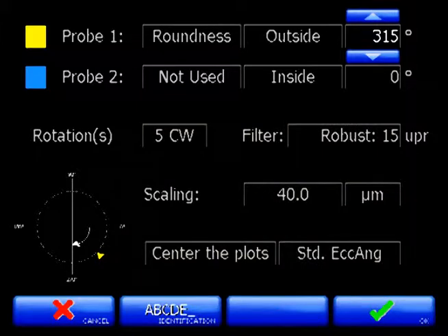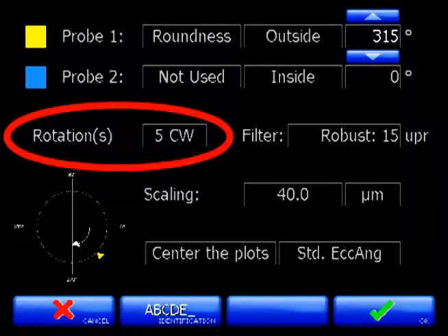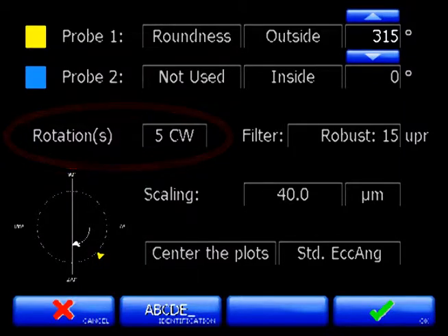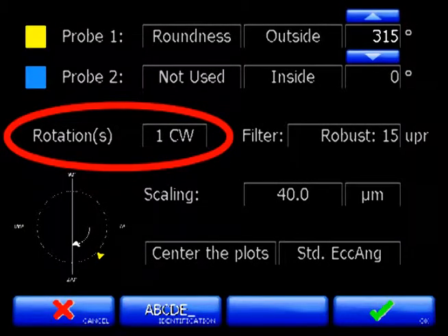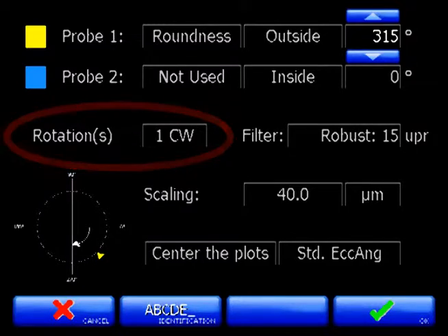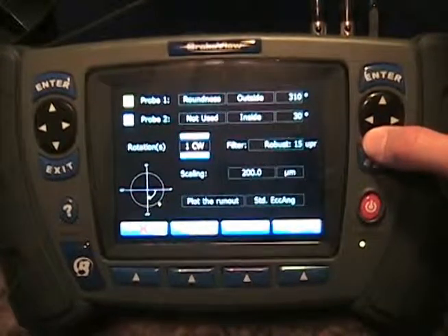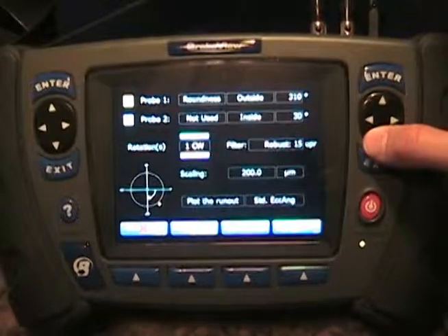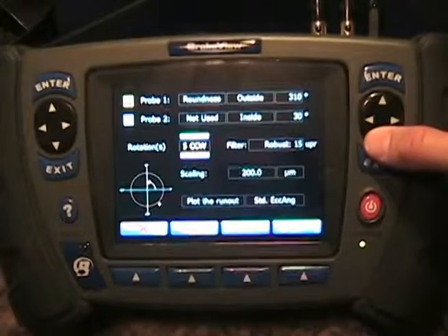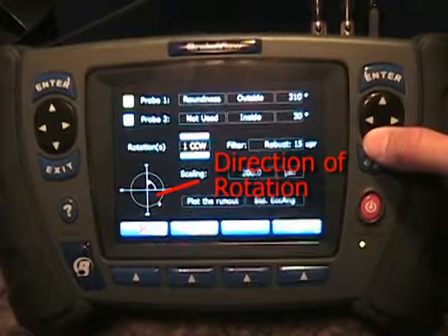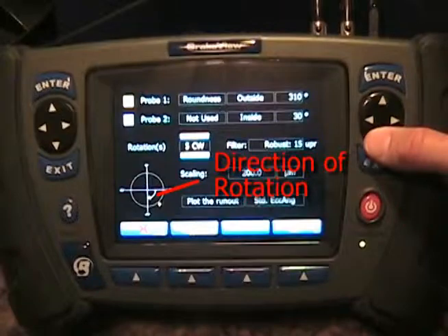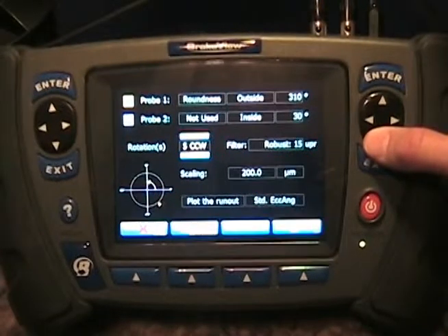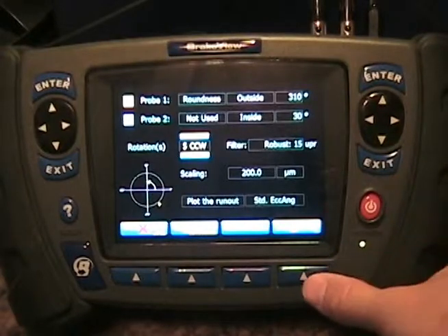The last measurement setup item is the actual type of rotation that we're going to use. If you recall in our brake rotor measuring video, we can hand spin a component and we would spin 5 rotations and use BrakeView's speed compensation mathematics. Another type of measurement is a motorized measurement where we have constant speed and BrakeView only needs 1 rotation. The same is true in roundness measurement. We can choose 5 rotations, which will use speed compensation, or 1 rotation, which is a motorized measurement. And we can choose either clockwise or counterclockwise measurements. You might also notice that the direction of measurement is shown on the probe position indicator. So for this measurement, let's choose 5 counterclockwise rotations.